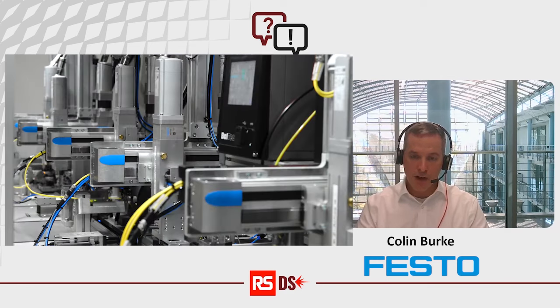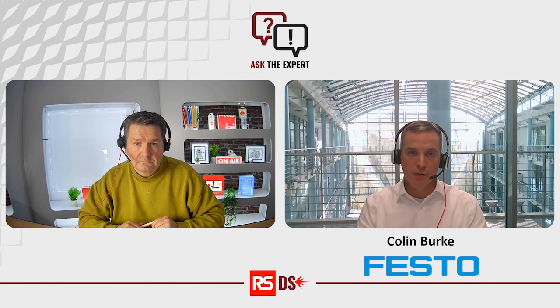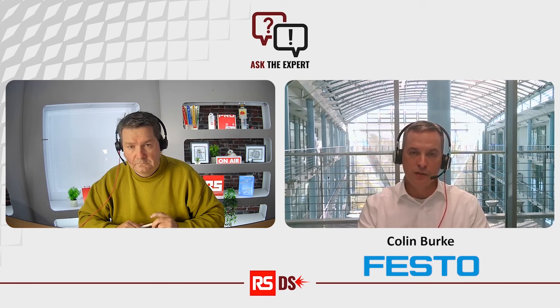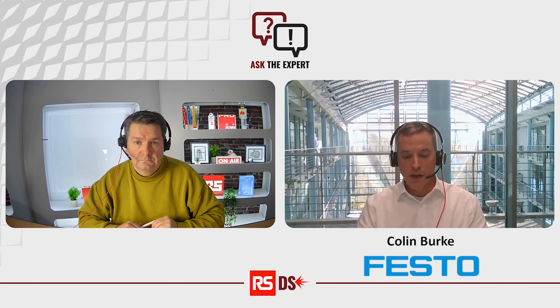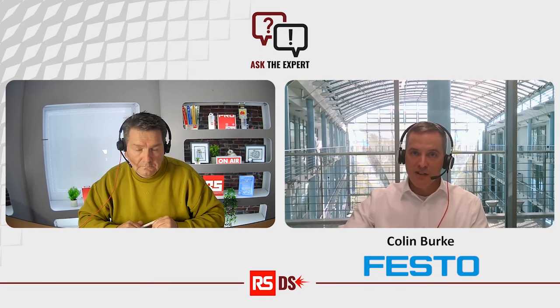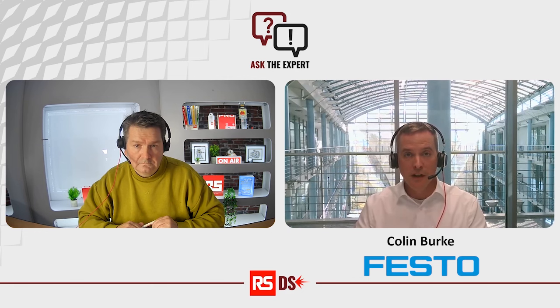So they have simple IOs, 24 volts, IO switching, and IO Link on board. And they have a very small and simple user interface, with 3 buttons and 10 LEDs on the outside. That's how you set up the speed, position, transition from movement to force, and all these kinds of things. So using a pneumatic thought process of putting pneumatics into the machine and wiring up the valve, it's basically the same steps. Note that the movement is electrical.